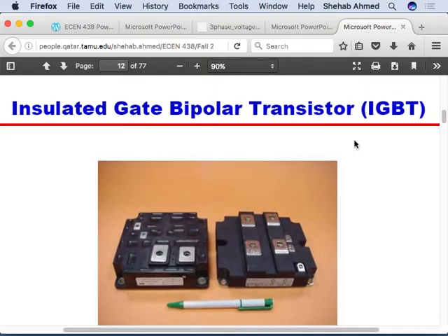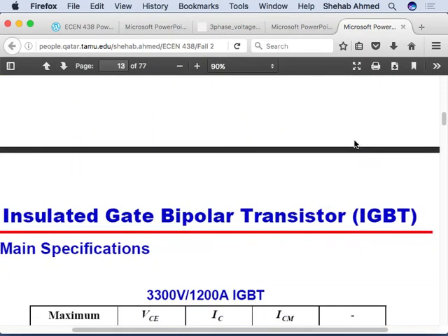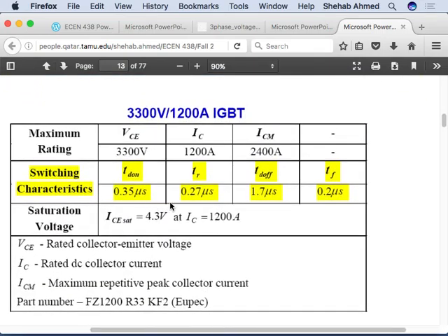Of course, the workhorse is the IGBT. Obviously, it's a very nice device because you can switch very fast. Let's look at this here. We're talking about 0.2 to 0.3 microseconds versus the 1,200 microseconds for the thyristor, right? Do you see why I can use this with many, many pulses per cycle? It just turns on a lot faster and turns off a lot faster, right?